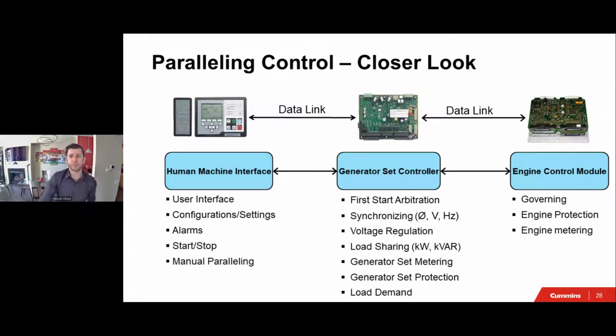So if we take a closer look, here we have the HMI, the human machine interface. It's a way for the operator to interact with the machine, a user interface: configure, look at the settings, receive alarms, start and stop the generator if they need to, and perform what's called manual paralleling. The generator set control, this integrated controller that is on the generator, is responsible for the first start arbitration, right? Which is basically dictating which generator set closes to the bus first. It's responsible for synchronization: phase, voltage, and frequency. So it has that synchronizer built in, and it's a 2-input synchronizer. So it's looking at the line side, and we need to connect the load side after that paralleling breaker. It's doing the voltage regulation, and then it's doing the load sharing, the kW and the VARs.